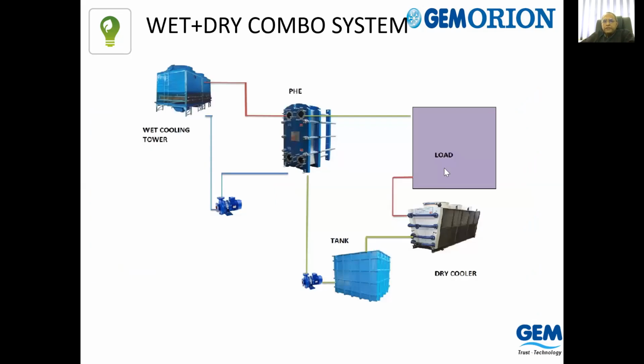So if you think of a combination system, the dry cooler can cool the water for the process till about 33 or 34 degree temperature, as long as the ambient is around 32, because in most places, throughout the year, if you consider, at least 60 to 70% of the time the ambient will be around 32, 33. So then the cooling tower system will be automated and it will not work. So this will be stopped. Only the dry cooler will work. So once the ambient temperature goes up, then the cooling tower pump and fan can start, reducing the temperature so that we can always maintain the desired temperature of the process even at increased ambient temperatures.